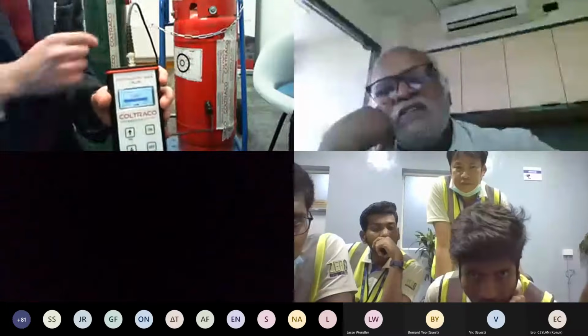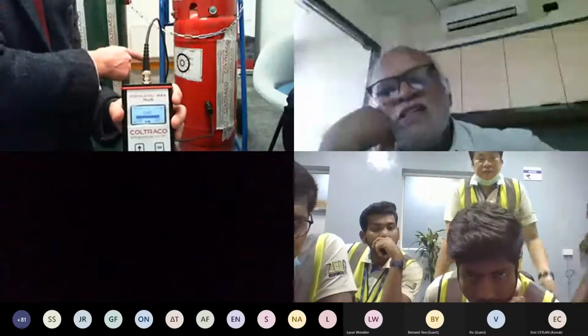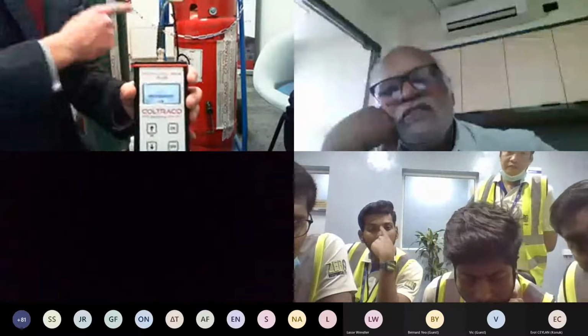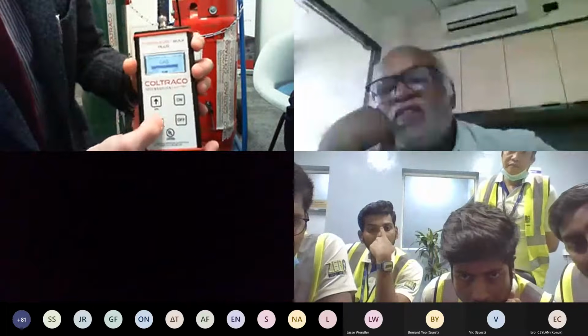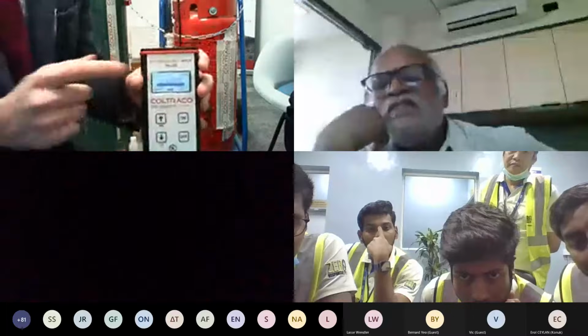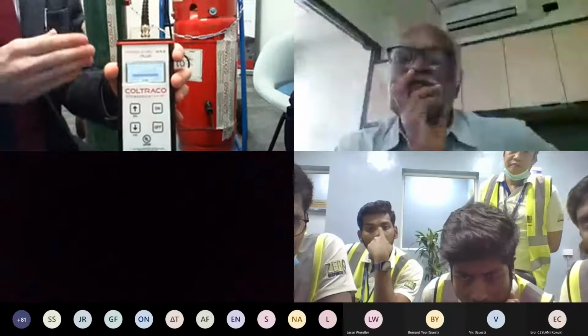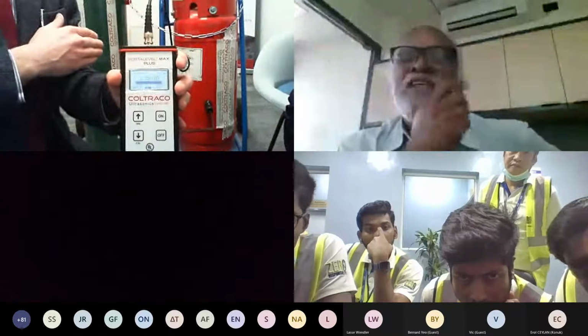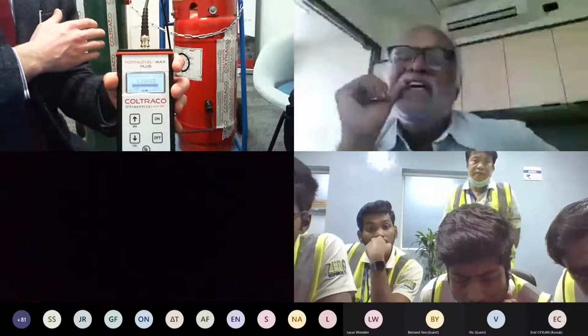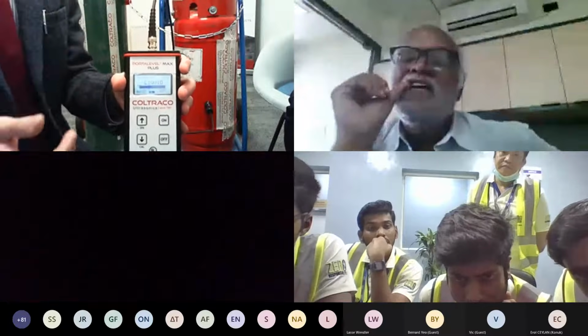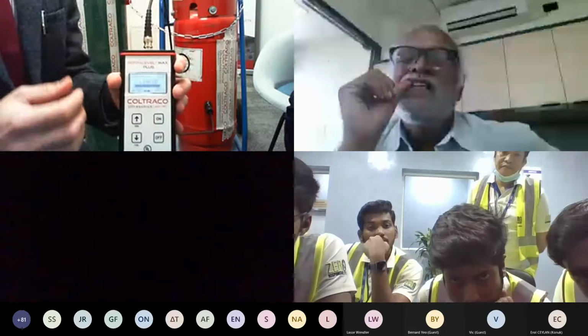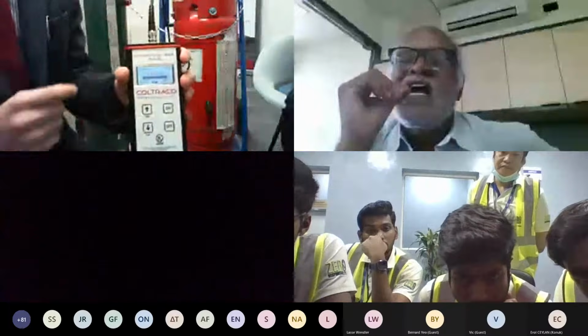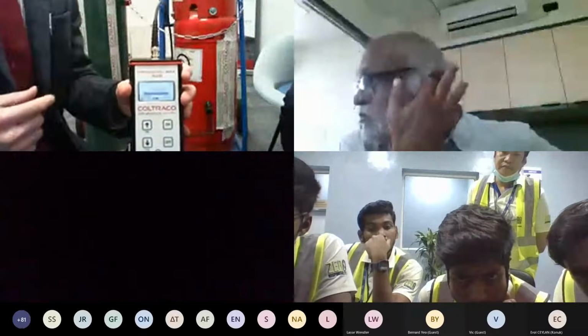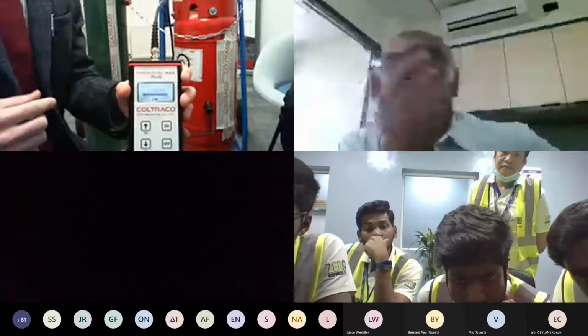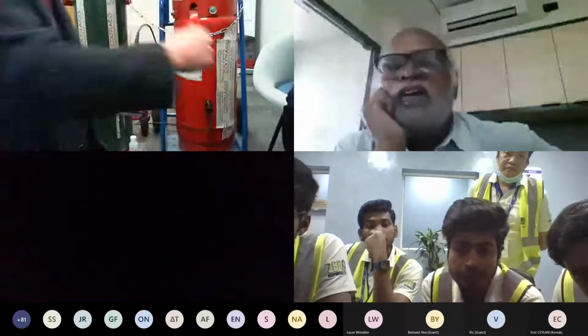In this case, because the high readings were found in the lower part of the cylinder in the liquid section, we press and hold Cal, and the unit switches to liquid. This is you telling the unit that you have found the high readings in the liquid section of the cylinder. So the procedure is the same. Now that I've pressed Cal, I'm using Cal 1 in this case. I will then move the sensor up in steps until that changes to gas, and I'll show you when it does.